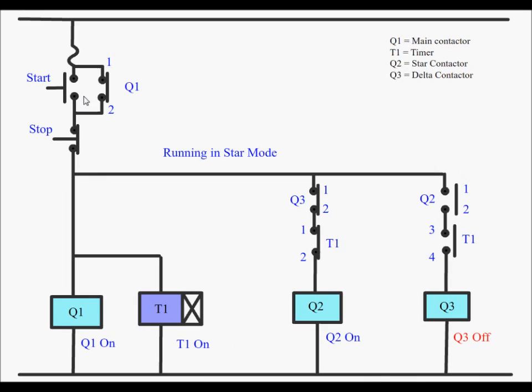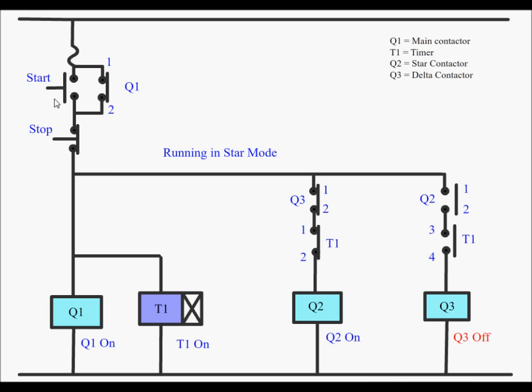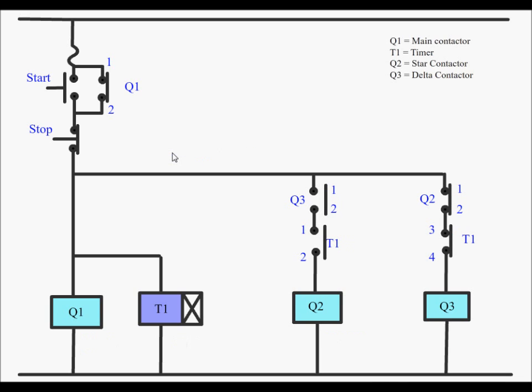This is the simulation of the control circuit. As you can see when the start button is pressed, Q1, T1 and Q2 are on and motor is running in star mode. After some time Q2 opens and as you can see Q3 is closed and now motor is running in delta mode.